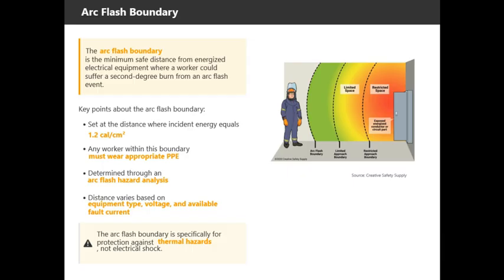The diagram you see here illustrates how the arc flash boundary is established around electrical equipment. Notice how the boundary creates a zone where special precautions are required. Here are the key points about the arc flash boundary. First, it's set at 1.2 calories per square centimeter because this is the threshold for a second-degree burn, the point where permanent injury begins to occur. Second, any worker within this boundary must wear appropriate PPE rated for the incident energy level at their working distance. Third, the boundary is determined through an arc flash hazard analysis, which calculates the incident energy at various distances from the equipment.